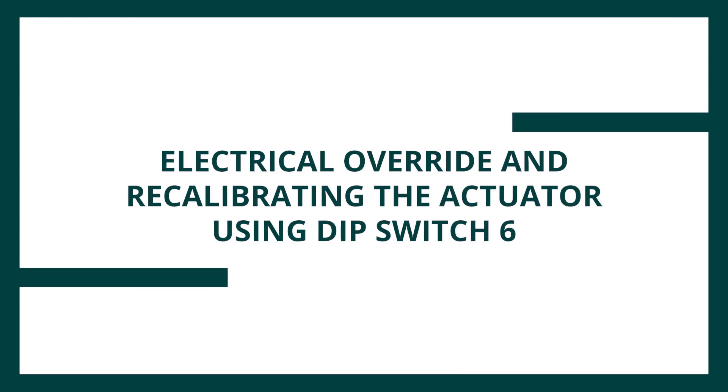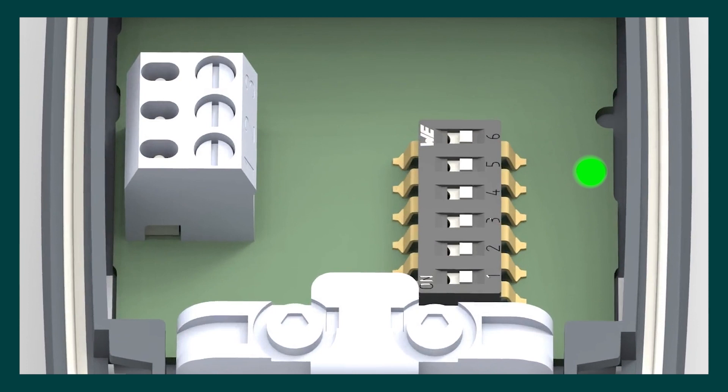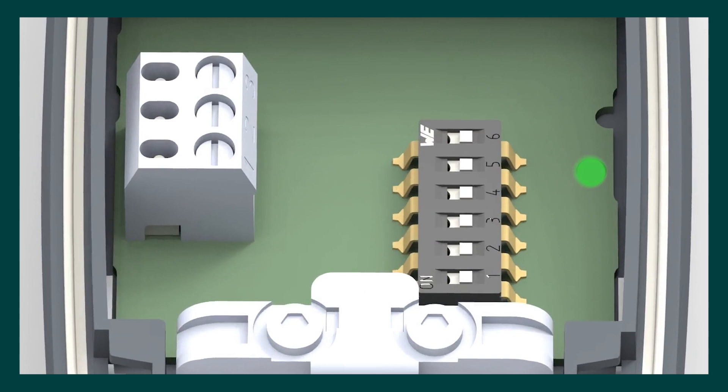To drive the actuator fully open, flip dip switch 6 from the off position to the on position. The LED will now flash red and green. After 10 seconds, flip the dip switch back to off. As well as driving the actuator open, this routine prepares the actuator for recalibration. Keep the actuator powered up for 360 seconds during calibration and after using dip switch 6. The actuator will close with the LED flashing green. Once closed, the actuator will be recalibrated and the LED will be solid green.